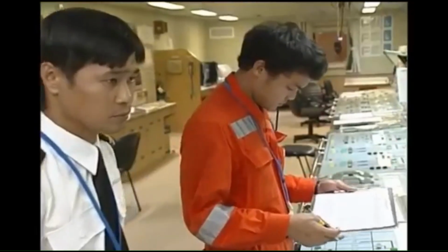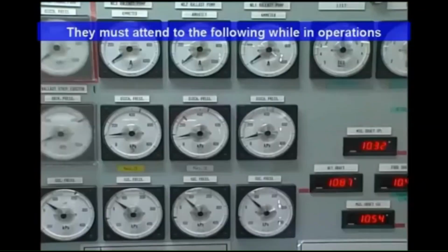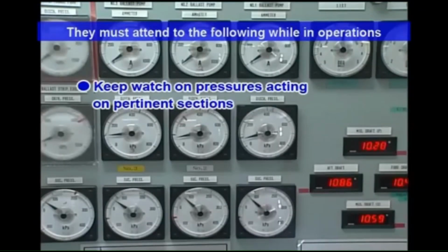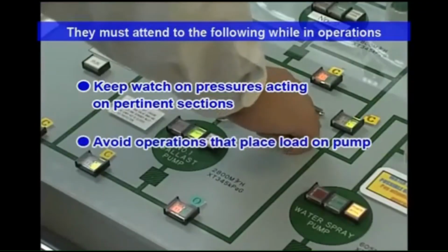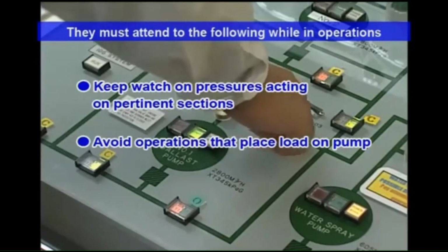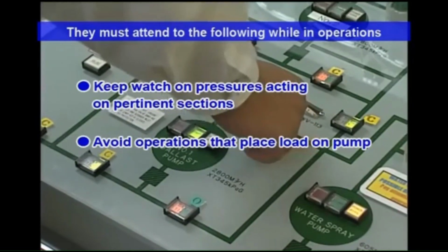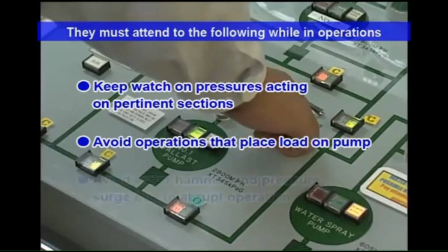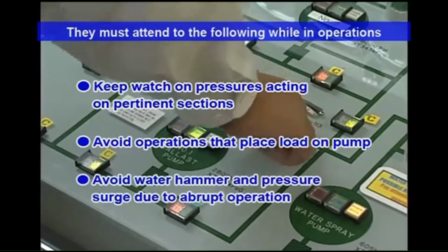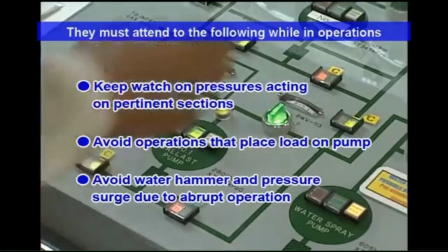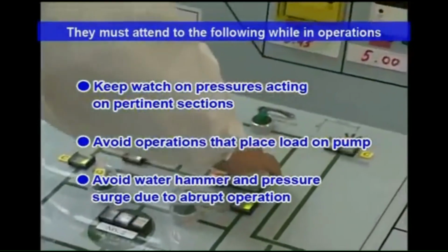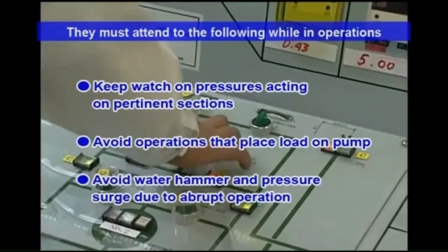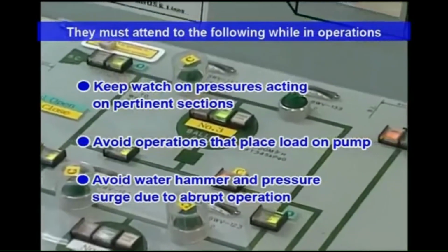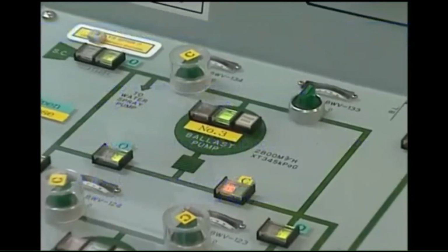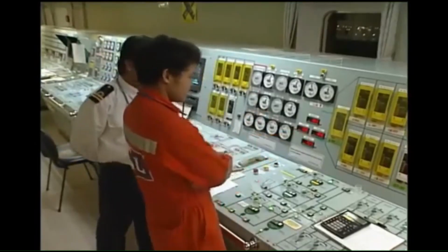Especially, they must attend to the following while in operation. Keep watch on pressures acting on pertinent sections. Understand the pump's principle and avoid load-placing operations, such as cavitation and air drawing. And understand valve characteristics and avoid water hammer and pressure surge due to abrupt valve operation.